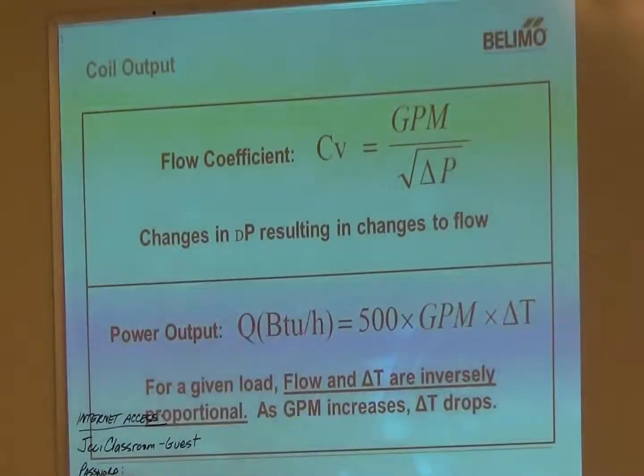Yes. This thing can be set up in about, I think, 12 different modes when you mix and match ons and offs. So it's a really smart valve. It's got a lot of features in it, but you can turn them all off, and you can buy this valve and put it in pressure dependent. So I can put it in as pressure independent, controlling on flow. I can put it in as pressure independent, controlling on BTU. Correct? Right. When I buy the energy valve, I get the temperature sensors, and that all comes with it. You do get it all, but you can use it as just a standard ball valve.